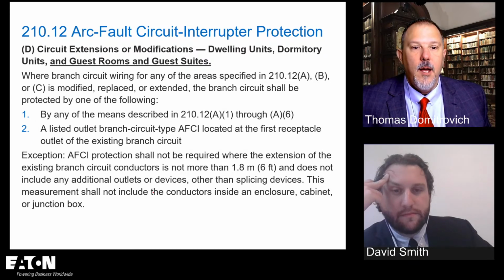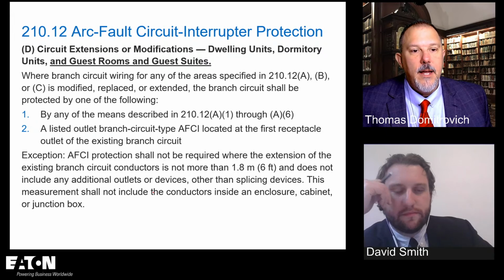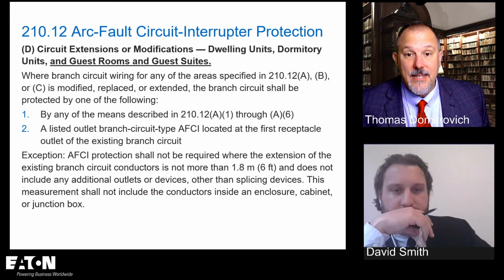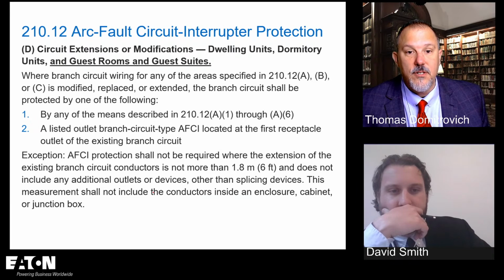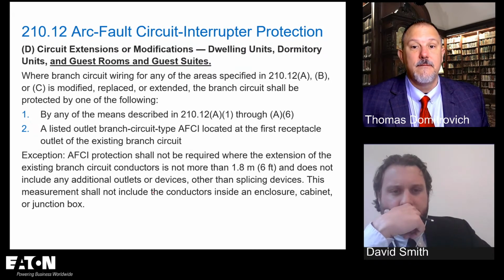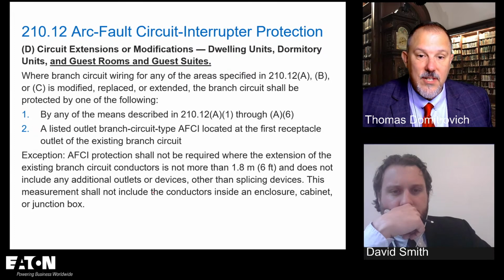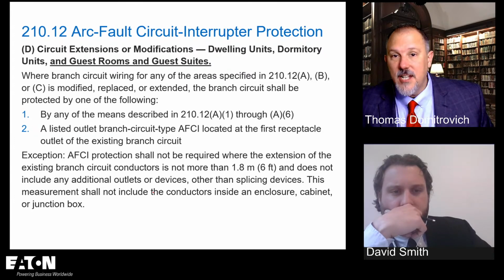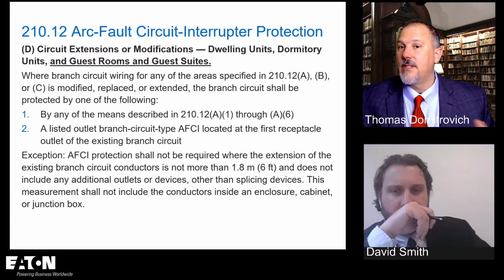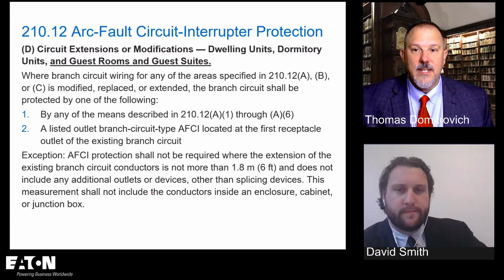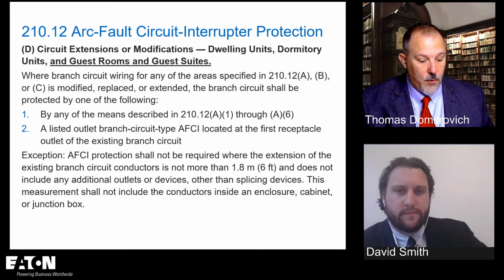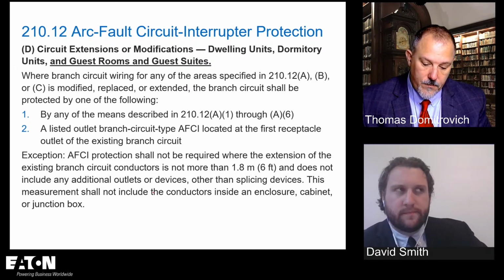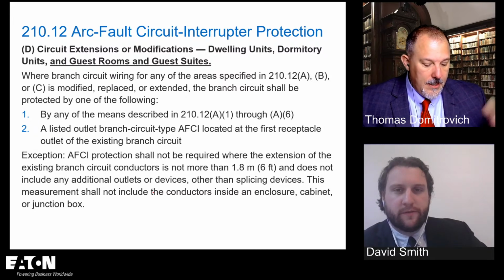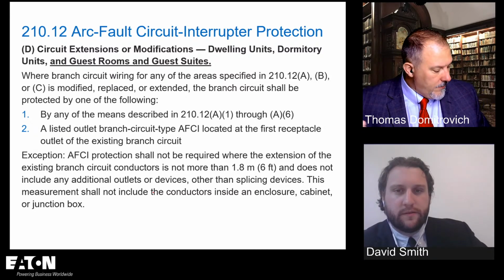But read the exception. AFCI protection shall not be required where the extension of the existing branch circuit conductors is not more than 6 feet and does not include any additional outlets or devices other than splicing devices. This measurement shall not include the conductors inside an enclosure. So I change out my panel board, my service entrance, I don't have to put AFCIs. I change receptacles out. We can argue because we can go back to 406. What is it, 406? 406.4(D), right.